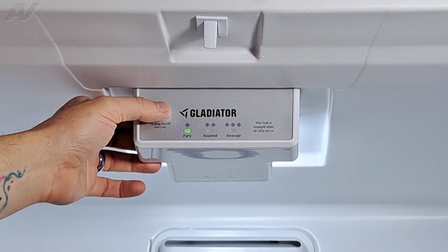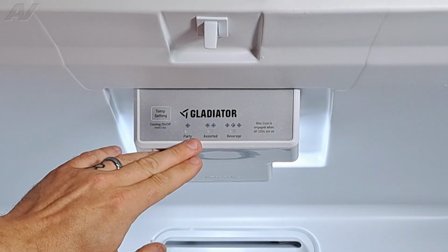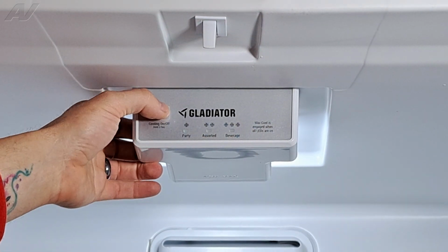This unit needs good air circulation in order for it to freeze. Otherwise, you might have some shelves maybe on the bottom that freeze and the ones at the top that do not. So if you're having cooling problems, do the cooling test, check the compressor, check the fan. If those are running okay, go ahead and press the button again. You'll see all the LEDs will turn off. And then once you press it again, LED 4, which is the middle LED, will illuminate.